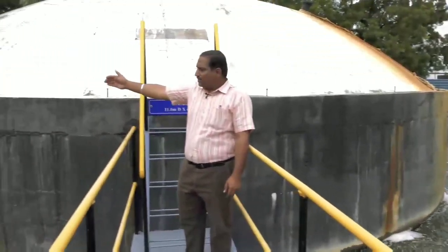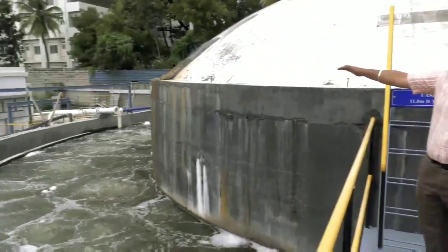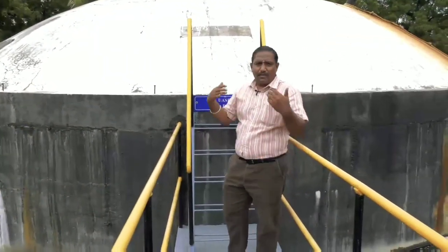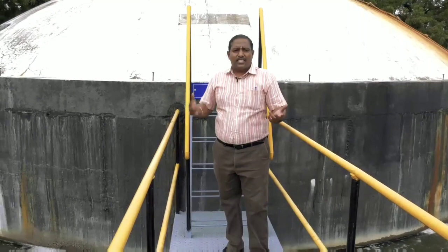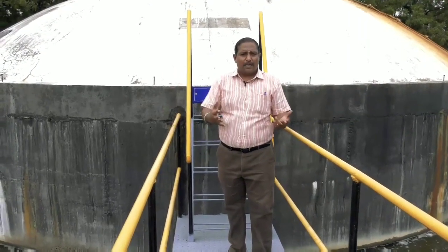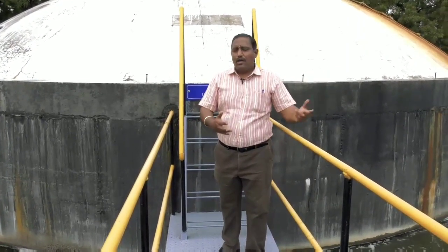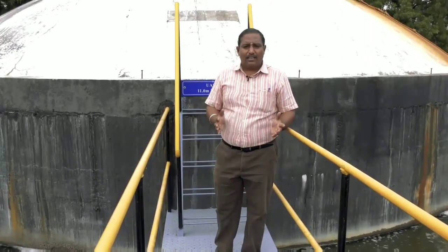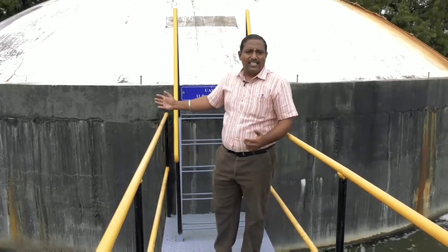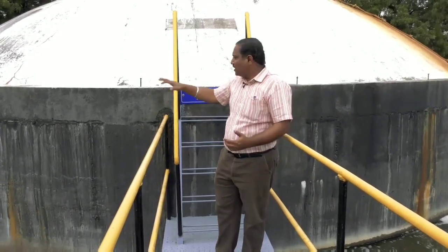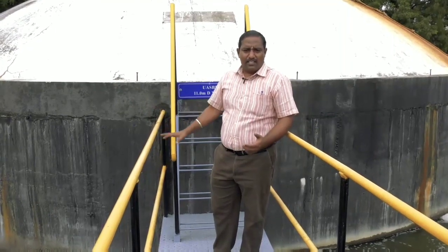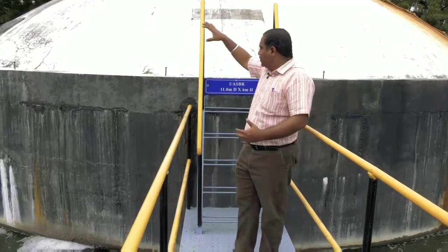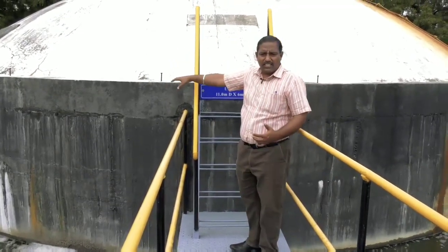So after the wastewater or sewage enters the collection sump, it is pumped to the next stage of treatment. As I have already mentioned, there are different stages of treatment. It starts with preliminary treatment, next is primary treatment, secondary treatment, tertiary treatment, like that I have told. But in the case of sewage treatment, we need not go for the primary or chemical treatment. We can directly go for the secondary treatment or biological treatment. That is what you can see in this treatment plant. From the collection sump, the sewage is pumped to the biological treatment process, or the secondary treatment.